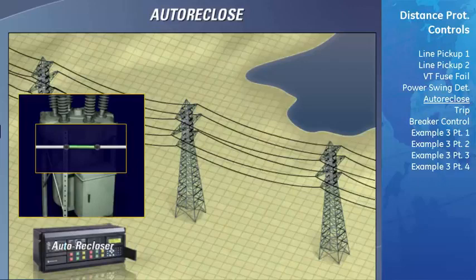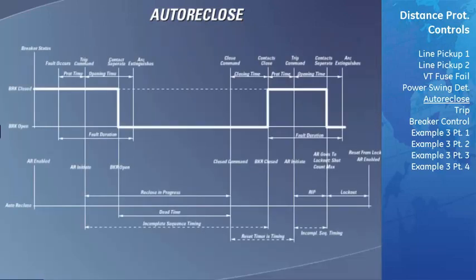In the D60, this feature has the ability of controlling the closing of one phase of a breaker at a time or closing all of the phases simultaneously. Quite often you will see a phase that can be tripped independently referred to as a pole. For this course, only the three-phase reclosing part of the recloser will be covered. We will now describe the operation of the auto recloser and how some of the settings affect its operation.